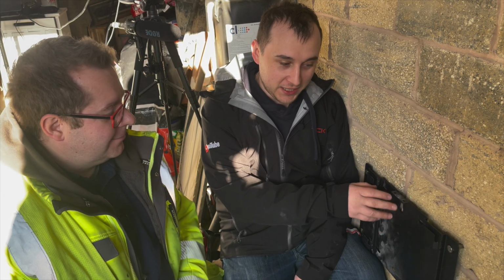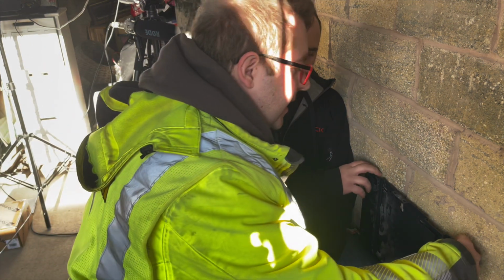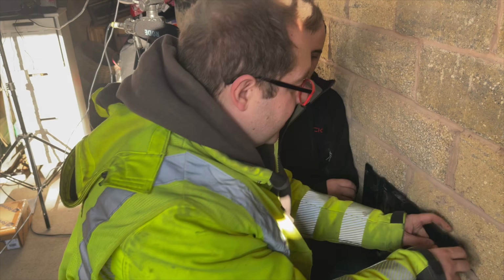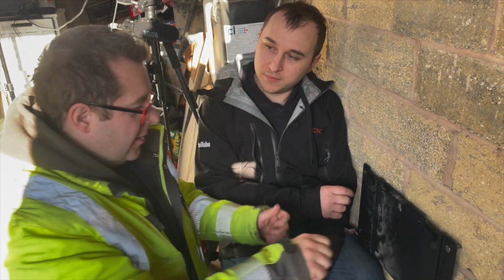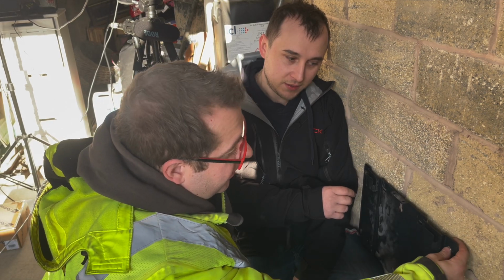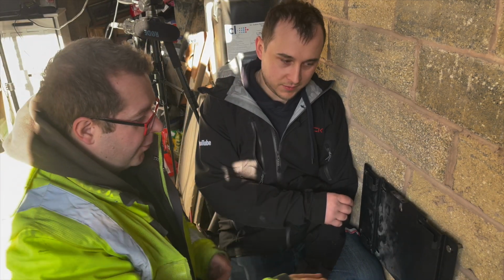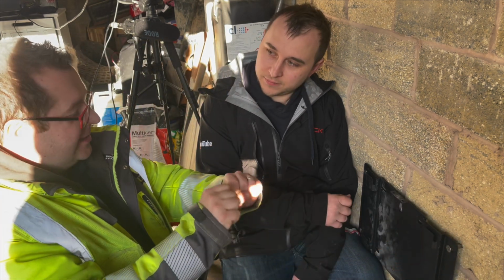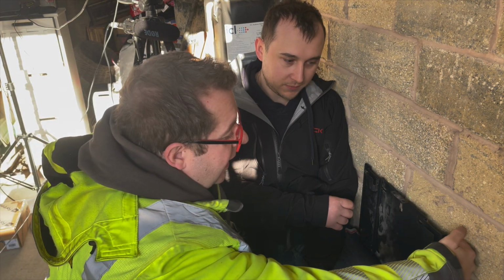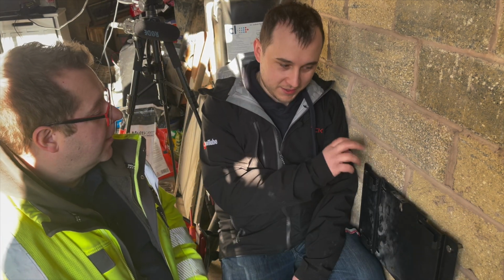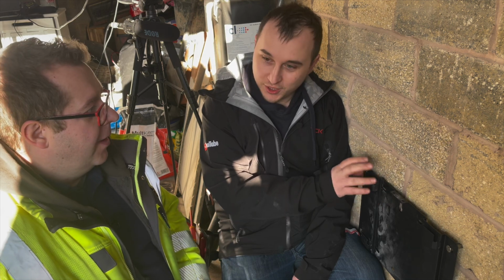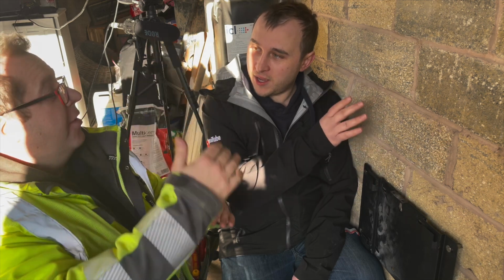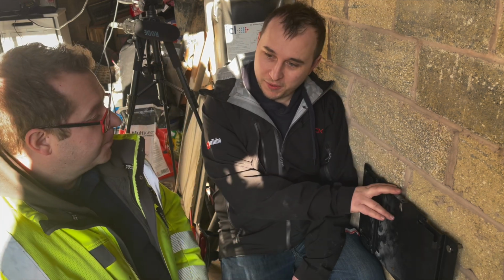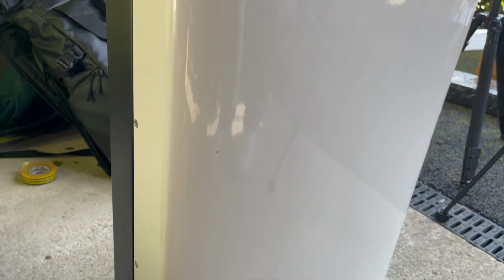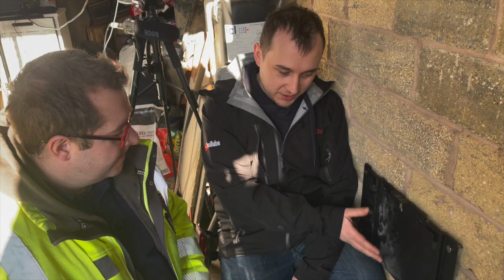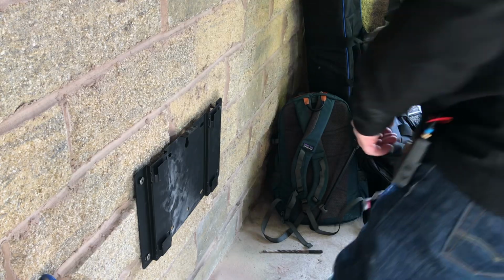So Lee, you've ended up putting it on the wall, but you didn't use any spacers. Why was this? So these expansion bolts, they've got a hard stop, so we can get the bolt with the brackets the correct distance off the wall. So when we tighten it up, it expands out and locks the bolt in position with adequate space. Okay, so that's basically fixed the issue that we're going to have. Yes, and we just need to copy the same thing above, so they're standing out at the same distance. Are we going to put the battery on this now then? Yeah, I think we should do, so we can make sure we've got the spacing right for the next part, and also that it's spaced off the wall correctly for this.